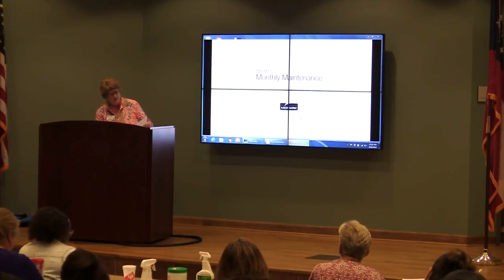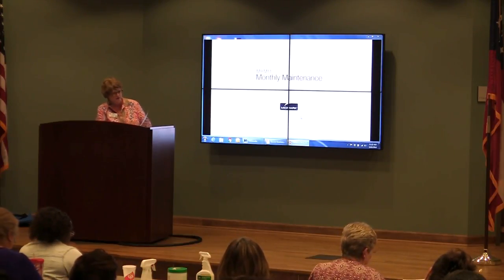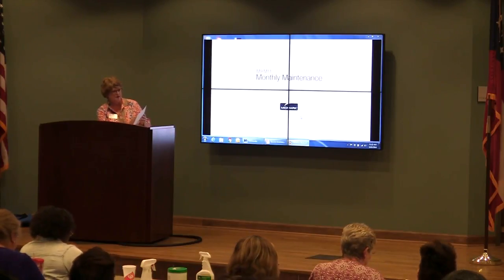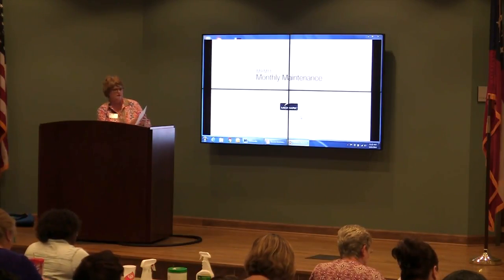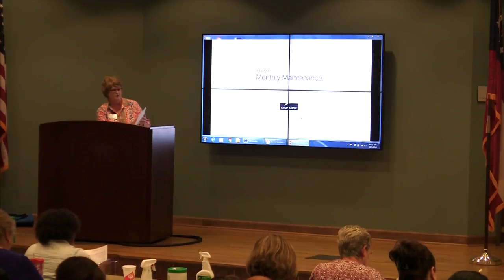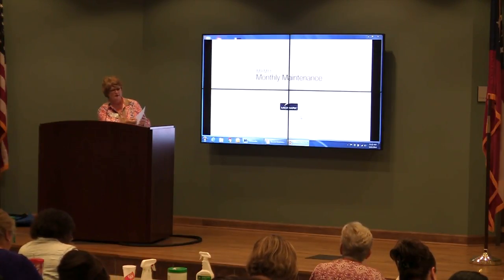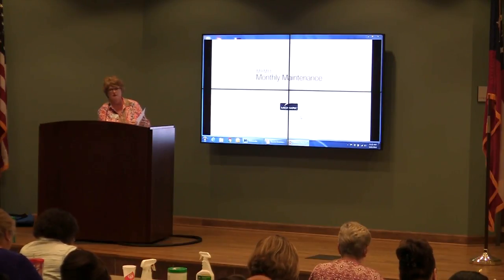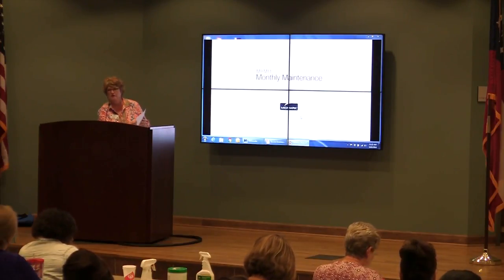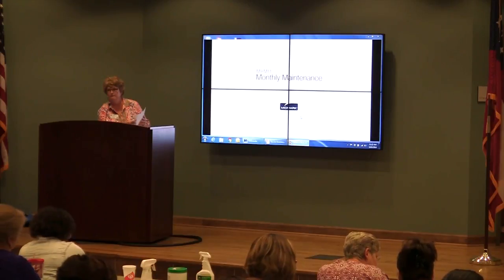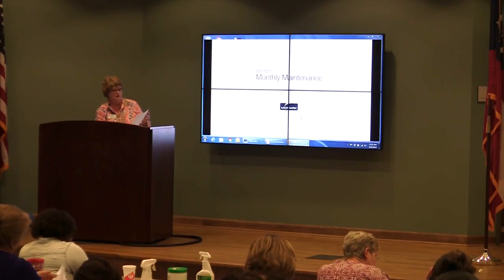And as you do the cleaning for the weekly autoclave maintenance, it gives you your steps, tells you what's needed to be done. You're gonna clean your external surfaces, you're gonna do your chamber wipe down, you're gonna clean your door gasket, you're gonna drain and refill the water. And where it says initials, I want you to cross out initials, I want you to sign it, not just initial it. And make sure you do that in your book.